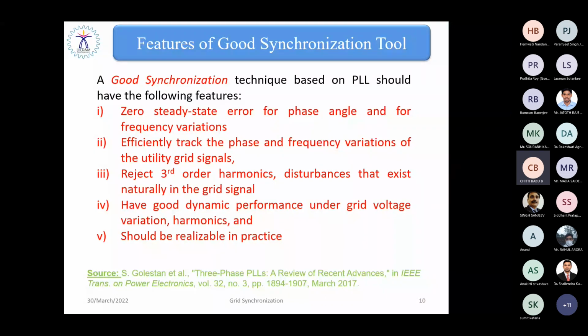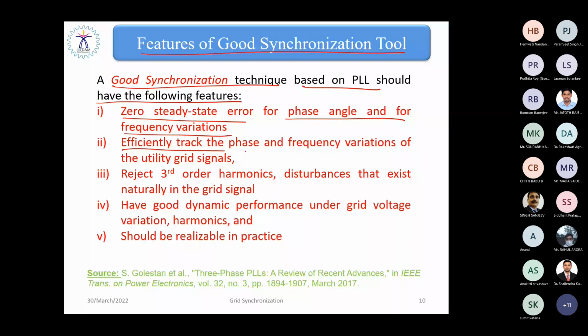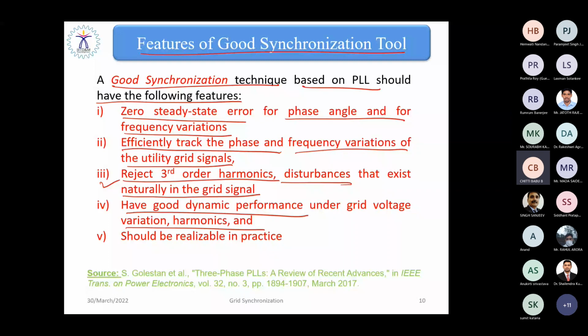The conclusion from that literature is that a good synchronization technique based on the phase lock loop should have the following features. First of all, it should have a zero steady state error for the phase angle and for frequency variations. It has to efficiently track the phase and the frequency variation of the utility grid signal. It forcibly rejects third order harmonics and disturbances that exist naturally in the grid signal. It should have good dynamic performance under grid voltage variations or frequency variations or during high frequency harmonic injection. In addition to that, it should be realizable in practice. So these are the important features of a good synchronization tool.